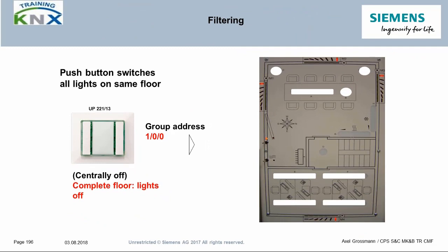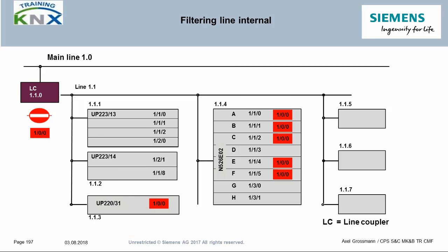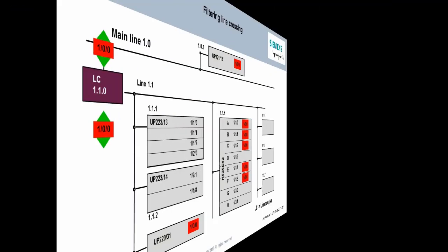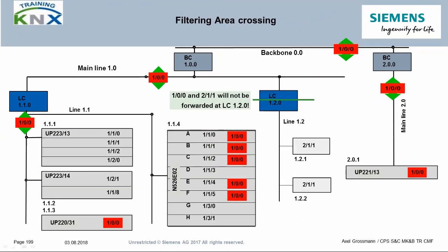With the information learned in this chapter, you can now proceed to perform the practical lesson for line-crossing communication. The task is to control all lights in the gamma training kit by using a push button on the main line. We did the central off control already, but only line-internally. The line coupler in this situation does not forward the telegram on group 1/0/0. Now, with a push button on the main line using group address 1/0/0, the filter table of the line coupler gets an entry on this address, so the related telegrams are forwarded in both directions. In a bigger network, the path for telegrams using the same target group address is properly built by ETS and transferred into the corresponding couplers' filter tables.